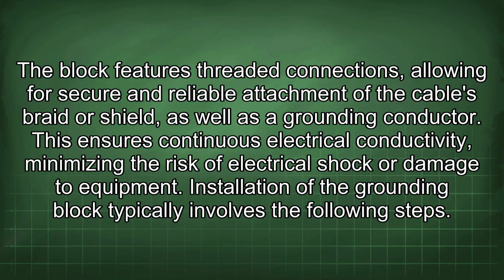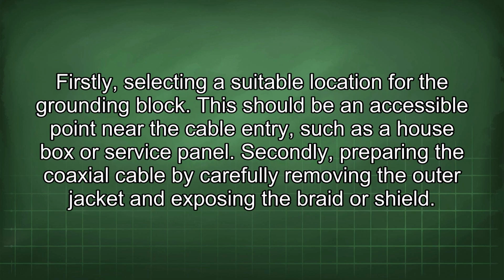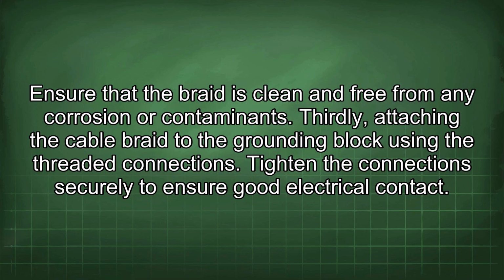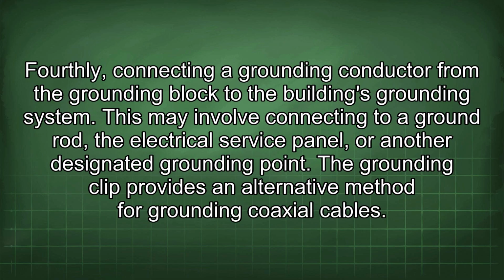Installation of the grounding block typically involves the following steps. Firstly, selecting a suitable location for the grounding block. This should be an accessible point near the cable entry, such as a house box or service panel. Secondly, preparing the coaxial cable by carefully removing the outer jacket and exposing the braid or shield. Ensure that the braid is clean and free from any corrosion or contaminants. Thirdly, attaching the cable braid to the grounding block using the threaded connections. Tighten the connections securely to ensure good electrical contact. Fourthly, connecting a grounding conductor from the grounding block to the building's grounding system. This may involve connecting to a ground rod, the electrical service panel, or another designated grounding point.